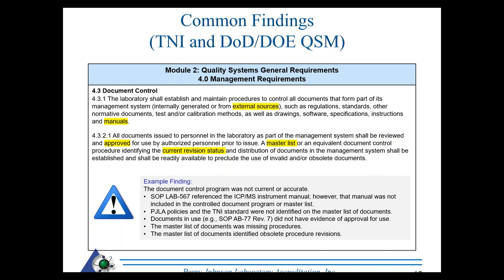There are also findings related to maintaining a master list of approved documents and current revision status. Common examples: an SOP refers to an instrument manual, making it a controlled document that must be on the master list; PJLA policies or the TNI standard aren't part of the master document list; documents lack evidence of approval for use; or the master list identifies obsolete revision numbers. If it's been updated recently, we use common sense, but significant tardiness results in a finding.